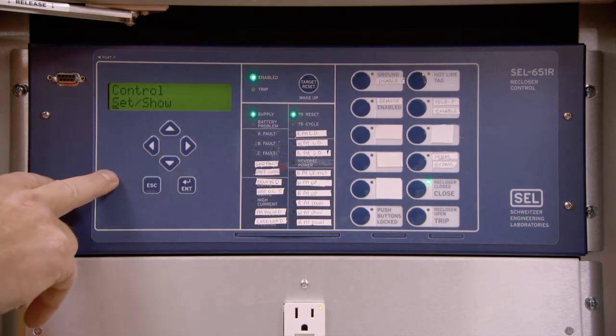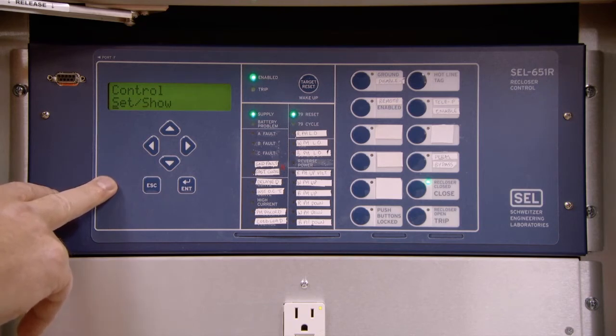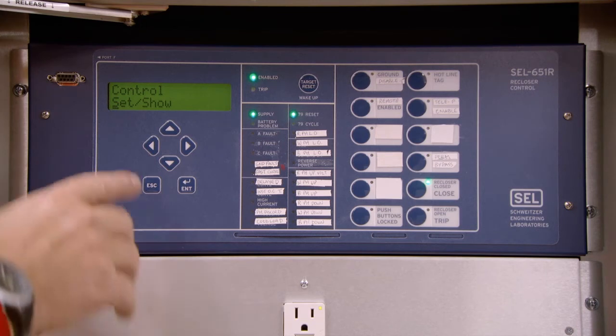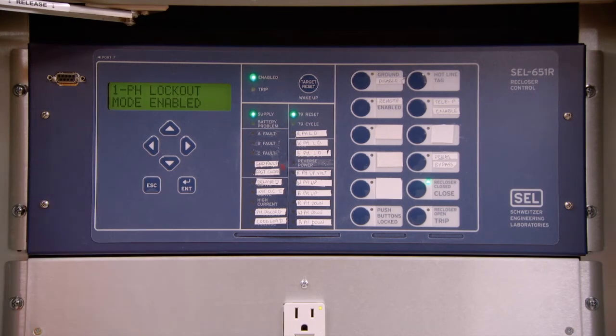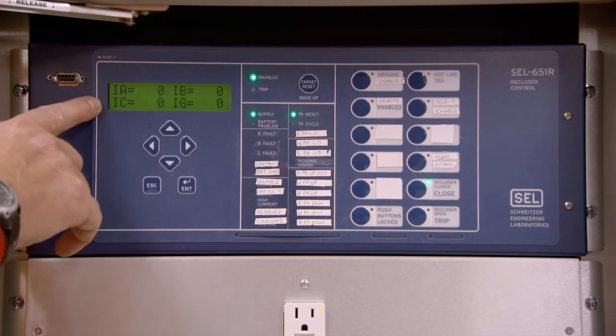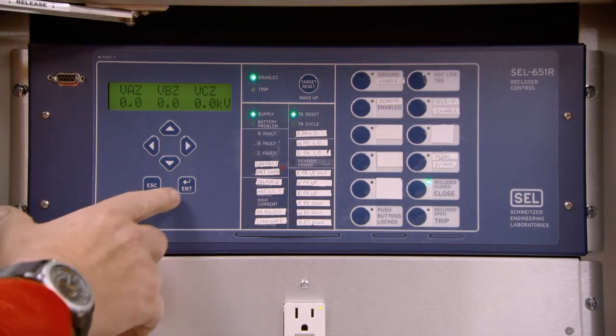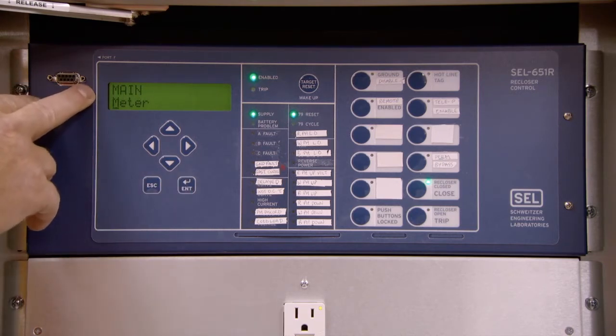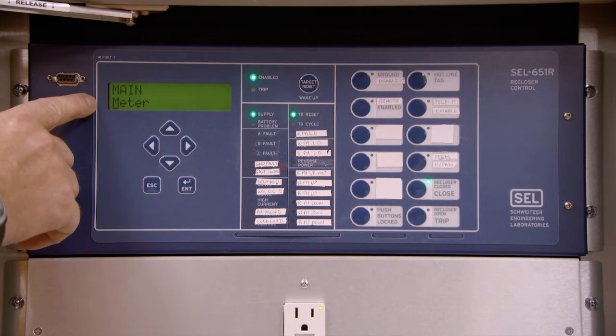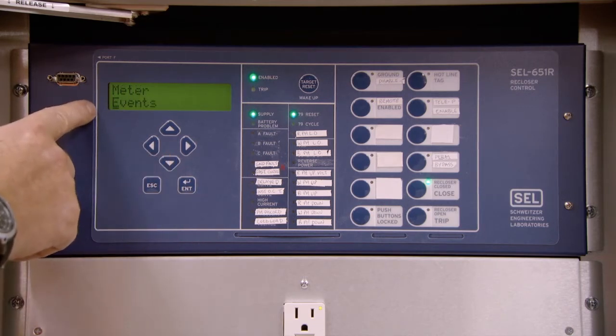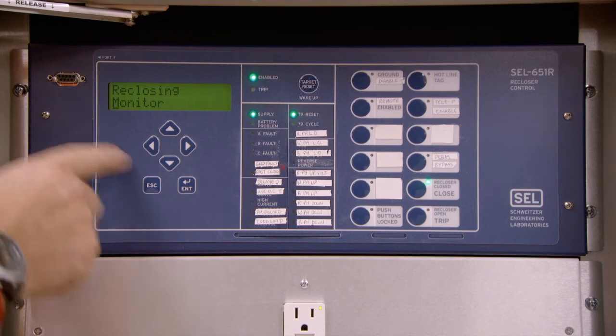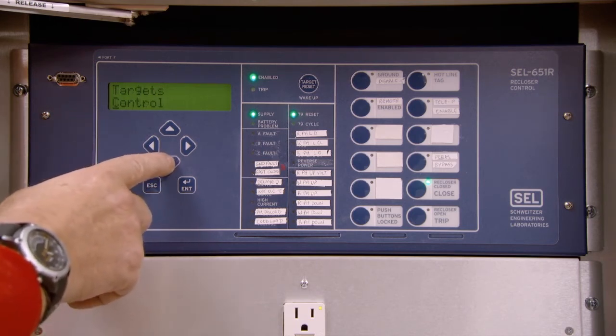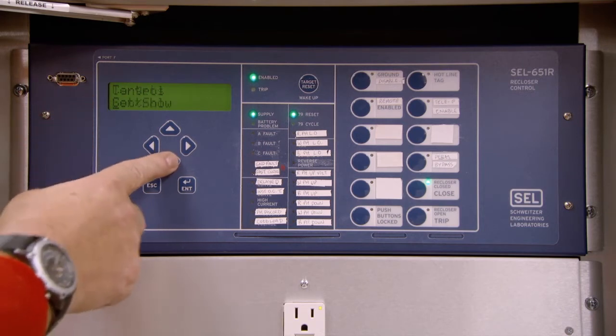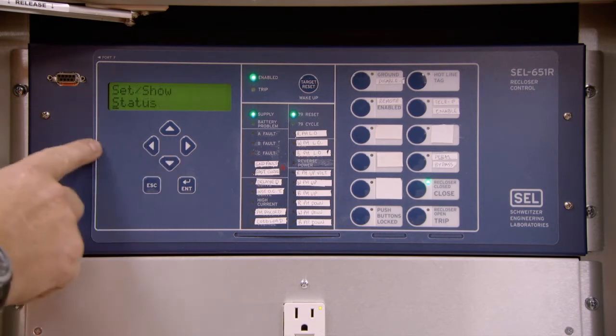You also have the functionality to be able to program this unit from the Set and Show menu and program individual items from the front panel. Let's go into an advanced setup on the scrolling screen. Upon pressing the Enter button, the screen will come up with various functionalities, such as Meter, Events, Reclosing features, Monitor, Targets, Control, Set and Show, Status, and Reset Access Level 1.